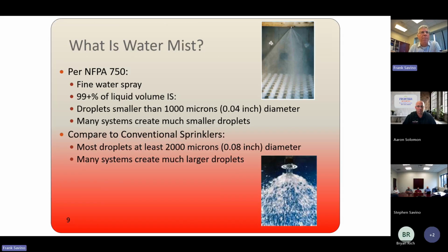All right. So what is water mist? Per NFPA 750, which is the standard that governs water mist, it's a very fine water spray such that 99% of the liquid volume is in droplets of 1,000 microns diameter or less. So 1,000 microns is about 0.04 inches. Most water mist systems actually create much smaller drops. When you compare that to conventional sprinklers, most of the droplets in sprinklers are about 2,000 microns or bigger, which is 0.08 inches. And a lot of sprinkler systems create much larger drops, actually.